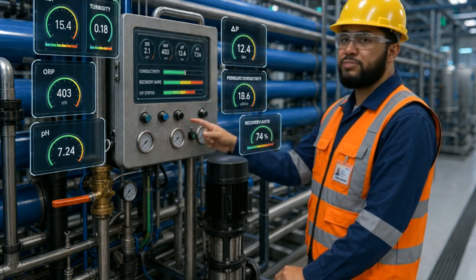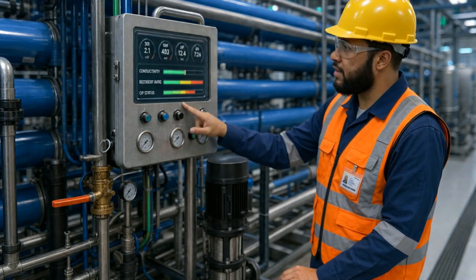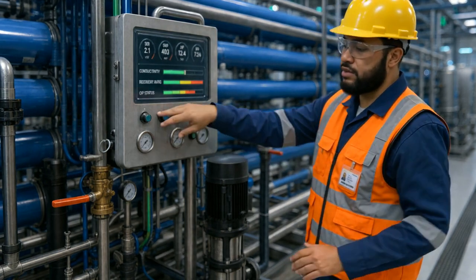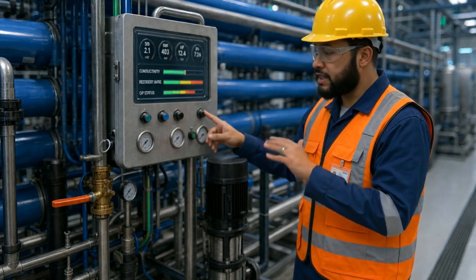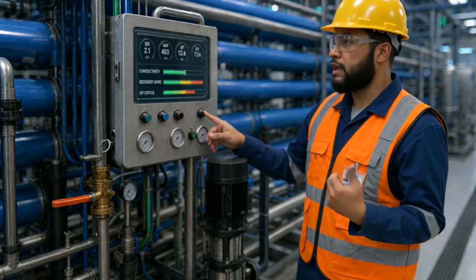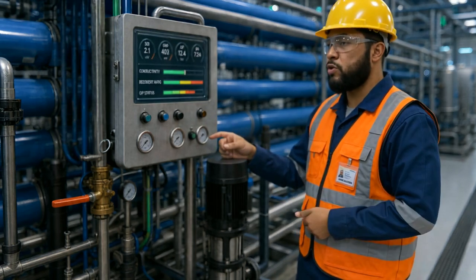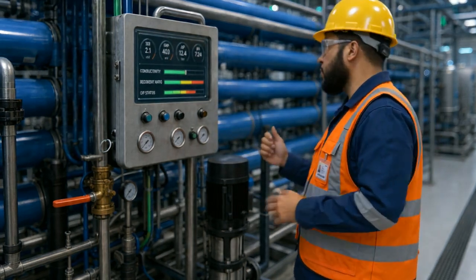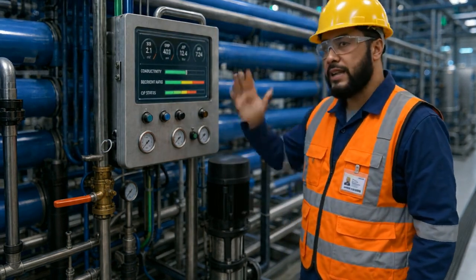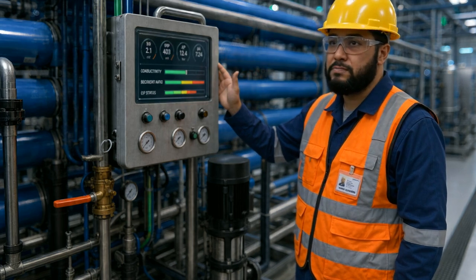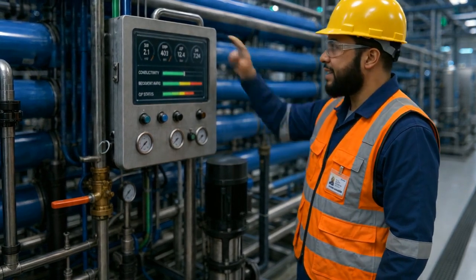Third, track differential pressure across each stage. A rising delta P is one of the clearest early warnings of fouling, scaling, or blocked feed spacers. Fourth, monitor permeate conductivity. If conductivity increases unexpectedly, salt rejection may be falling, a membrane may be damaged, or an O-ring may be leaking. Finally, control recovery ratio. Higher recovery improves water yield, but if it is pushed too far, minerals can exceed their solubility limits and crystallize on the membrane surface.